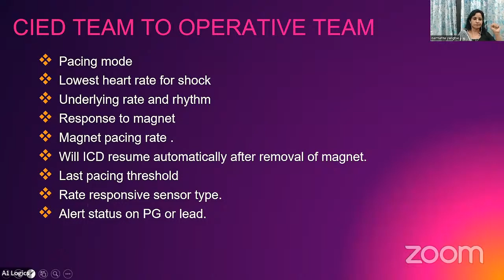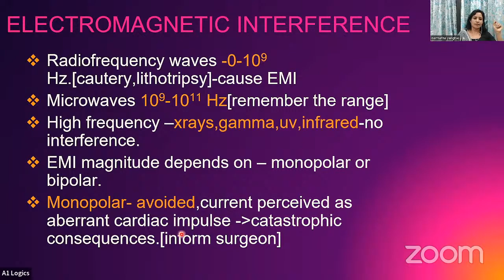Now coming to the electromagnetic interference. The electromagnetic interference in an OT is mainly because of the electrocautery or the diathermy. So you should know that radiofrequency waves in the range between 0 to 10 power 9 and microwaves in the range between 10 power 9 to 10 power 11 mainly cause electromagnetic interference. The high frequency range like X-rays, gamma, infrared, we need not bother about. So only this frequency will cause this problem. Whenever you are using electrocautery, monopolar is more dangerous than bipolar. Why? Because the monopolar current is perceived as an aberrant cardiac impulse.